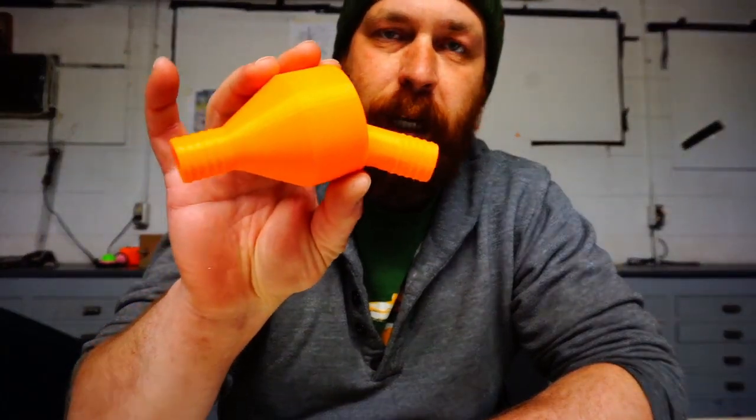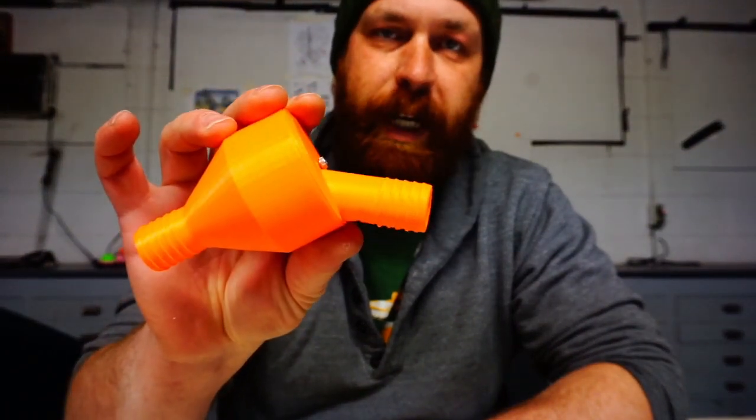I'm going to show you a diagram of a machine that I think could be built, and then I'm going to show you this valve, which is a PEEP release valve that maintains a positive pressure during exhale. I've got these files online right now. They're free and open source, in Onshape, so you can edit them.